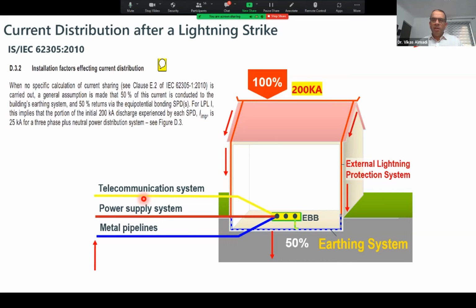When lightning strikes any building, it creates a surge, and how much of this flows through our lines, be it the power line, metal pipeline or telecommunication line, the ratio is 50 and 50. Only 50% goes to the earth and 50% goes to the power system, metal pipeline, or telecommunication system. So those who believe that good earthing can solve all the problems, consider these calculations which have come up after so many experiments worldwide, and IEC has adopted this formula for division of lightning current. So this much surge is expected on the power line or telecommunication line based on their resistance. Of course, it will be divided and we have to take measures accordingly.